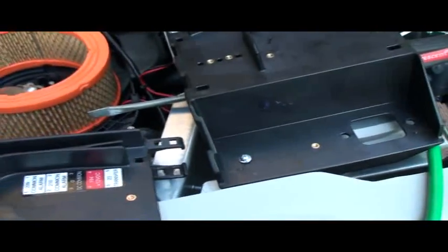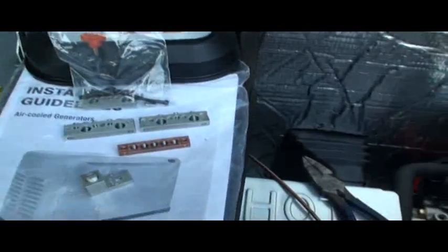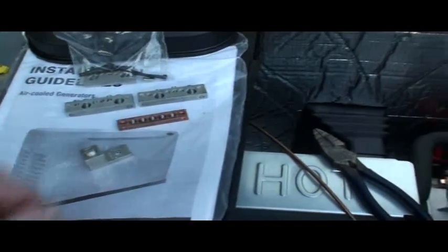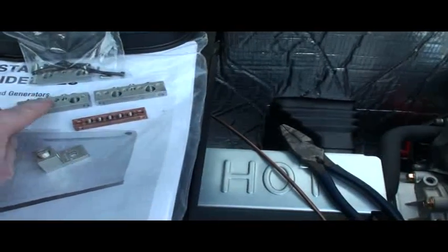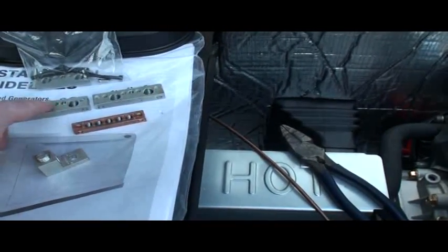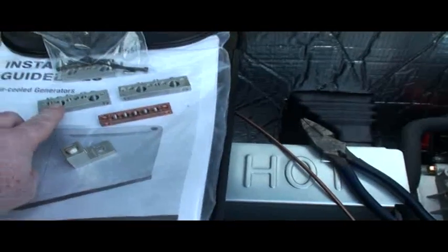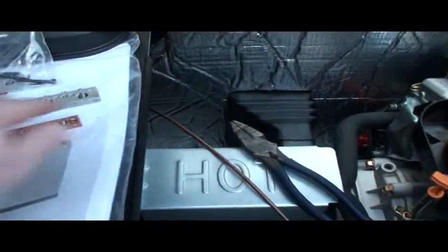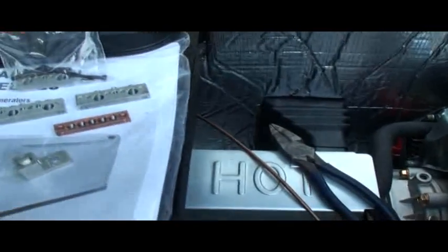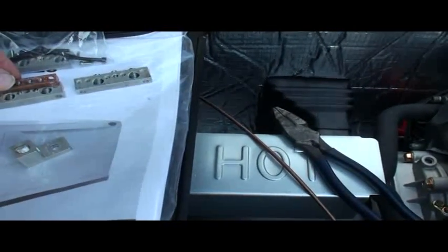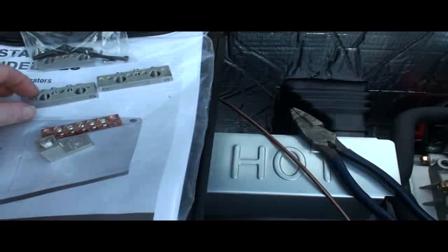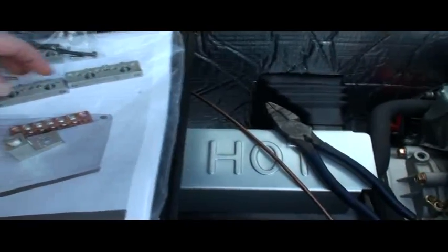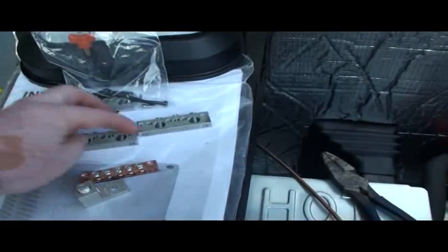The way that probably this should be fixed is that they should use ground bars that will accept the larger wire. So I got on the internet, and I looked around for places selling ground bars, and I found one that has multiple sized holes in it, as you can see here. This was all one bar, and I found that the holes line up so that I can have four small ones and two large ones, and the bolt holes will still bolt down correctly.